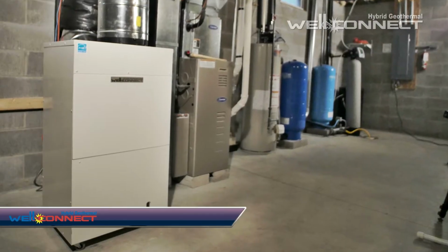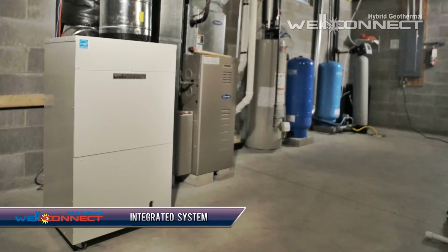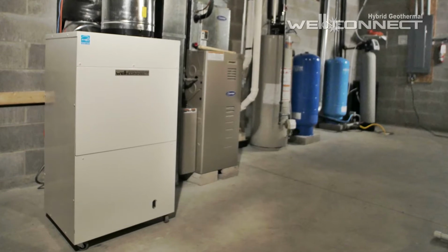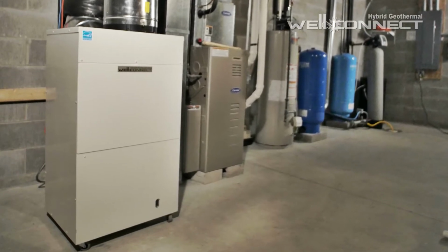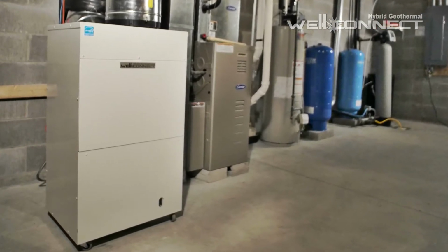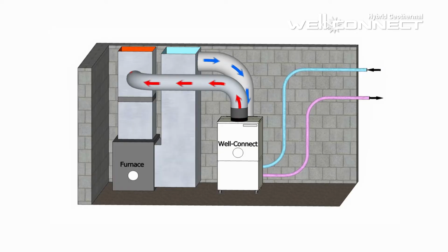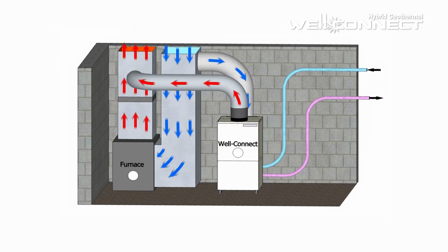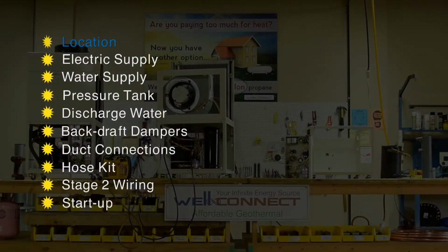The third and most common option, and the one you will see in this video, is the integrated system, where the WellConnect is set up to work in parallel with an existing fossil fuel-fired forced air furnace. Remember, in a WellConnect installation, the existing heating system is not removed. It remains in place as the source of Stage 2 supplemental heating and cooling or emergency heating if needed.